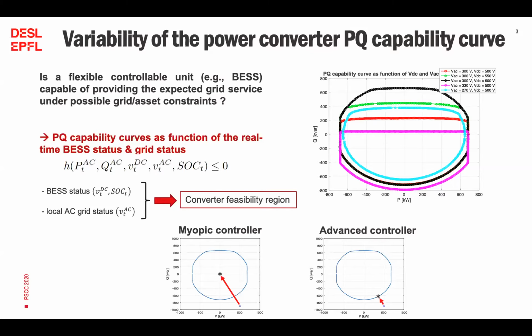Typically, in fact, in myopic applications, when setting a set point out of the capability of a converter, the converter will immediately trip, go into error, or it will simply set zero active and reactive set point, thus falling in a situation where the service is not delivered. In our case, we can assure that the service is fully continuously delivered by setting the closest possible feasible point.